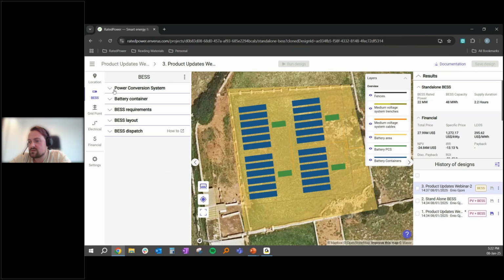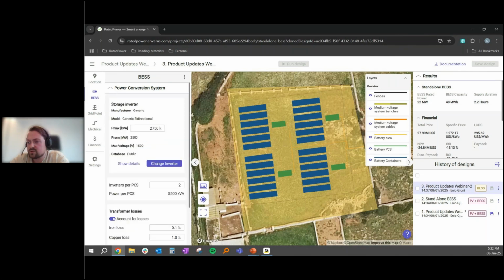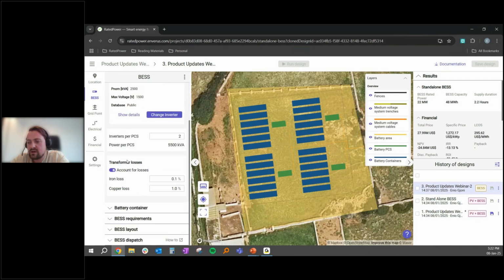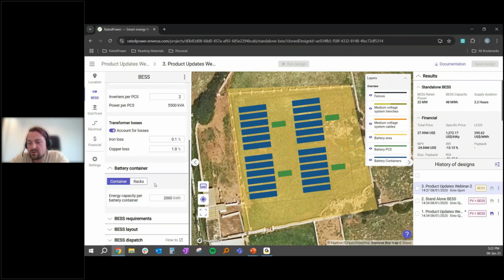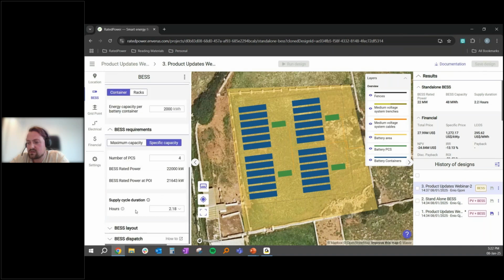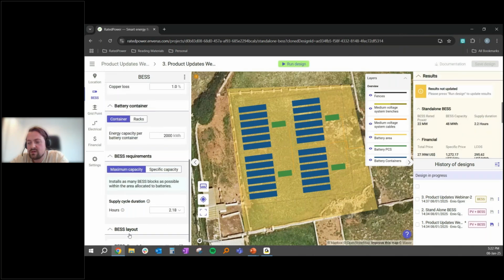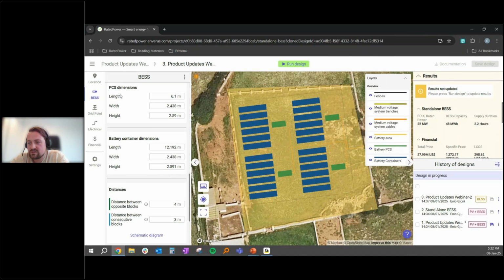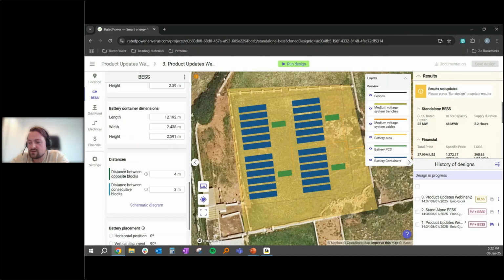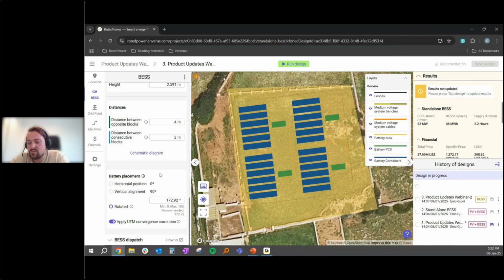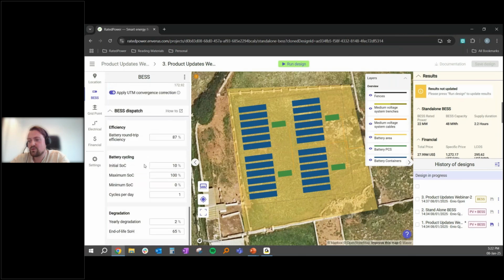In the BESS tab, users can edit the power conversion system by choosing the storage inverter and editing transformer losses for the energy calculation. They can change the capacity of the containers, add requirements for the battery by choosing a specific capacity to size it or choosing maximum capacity, and change the layout, PCS dimensions, battery container dimensions, and distances between blocks.